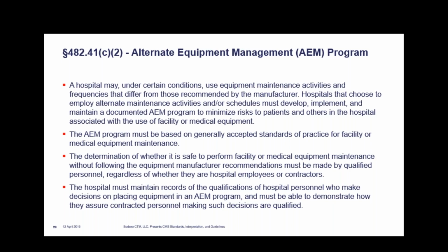I was just wondering, because I feel like part of the problem is the manufacturers, is there any pressure being put on them to decrease PM schedules? As technology has gotten better, the PM schedules have stayed the same. That's why we as a field don't want to do PMs as much, because we know they're not effective in a lot of cases. If we started with them and said, look, if it's not going to fail, why are you still doing it? Manuals say we need to do PMs every 6 months or whatever. We know the failure rates are going to be less because technology is better.